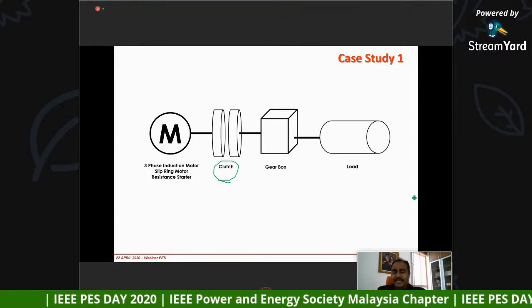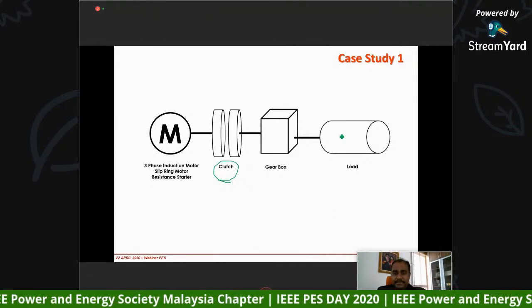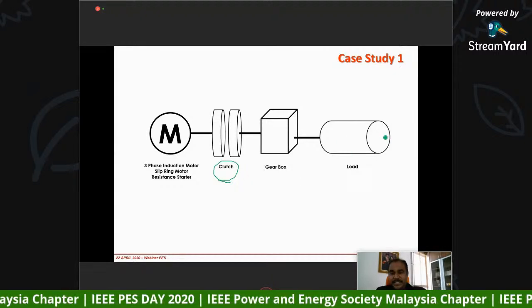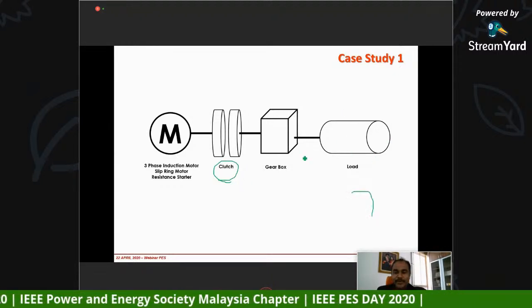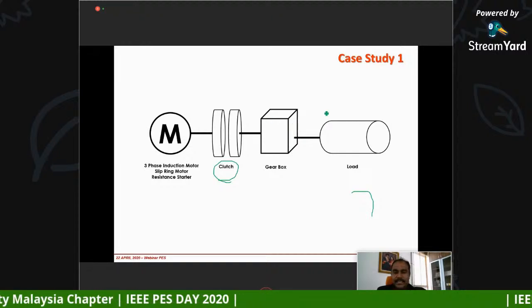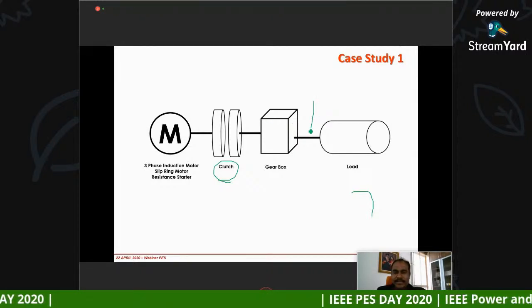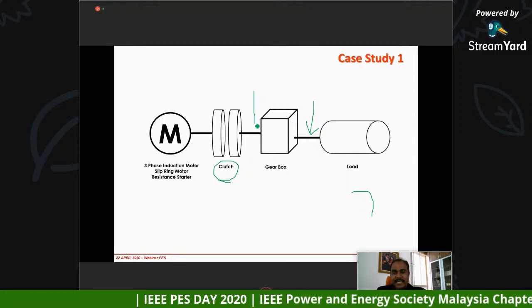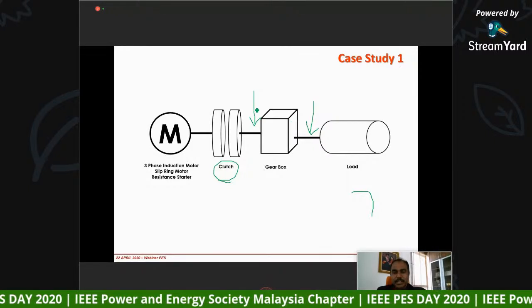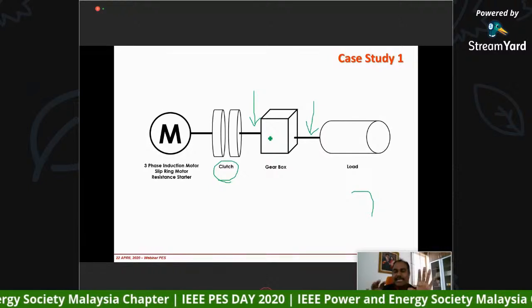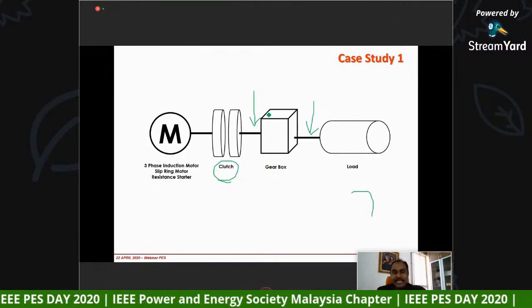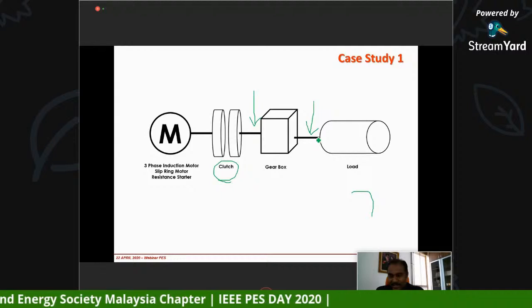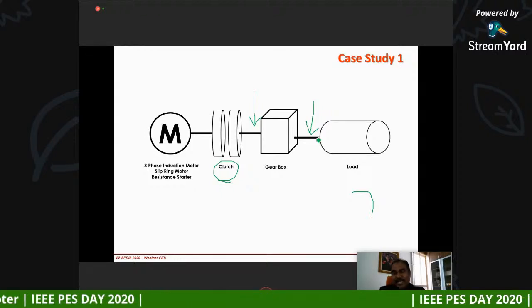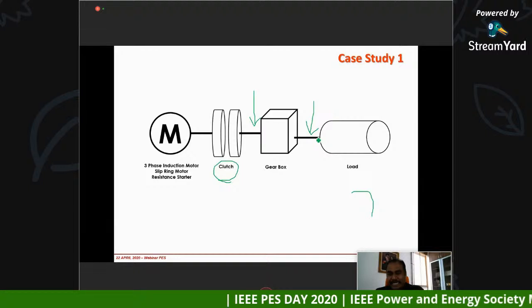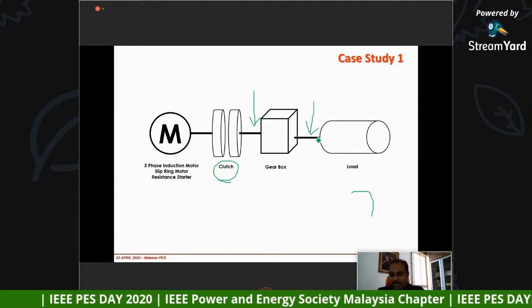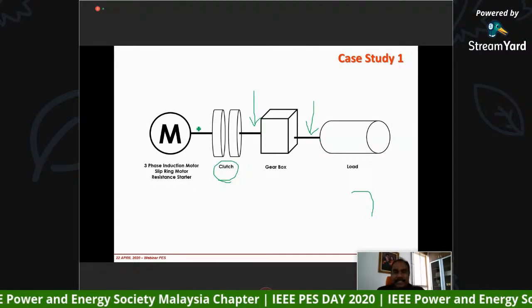So when you have this kind of system, you have to understand one thing. If you look at this, you have a gearbox here, and when we have a gearbox, we must understand that it is like a mechanical transformer. The gearbox is usually installed because they already calculated and designed from day one that they want to achieve a certain torque at the load. That's why it's running at a lower speed. They already calculated the speed and the torque requirement at the load side, and accordingly they sized the gearbox. So everything is already calculated.